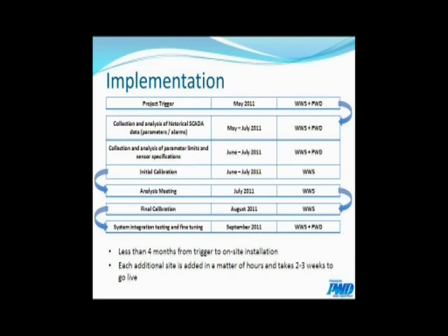And once the system was installed, PWD began classifying the alarms and working with Whitewater to fine-tune the software. The fine-tuning process was, I would say, generally 3 to 4 weeks. But even after that, results continued to improve in subsequent months as more alarms came up and additional settings were tweaked. And just to give you an initial time frame on things, the initial stations were installed within about 4 months of the trigger date, and then adding additional sites after the initial installation is generally quicker. Sites are just installed in a matter of hours through a WebEx session, and the fine-tuning generally takes a little bit less, maybe 2 to 3 weeks once you get that initial installation done.